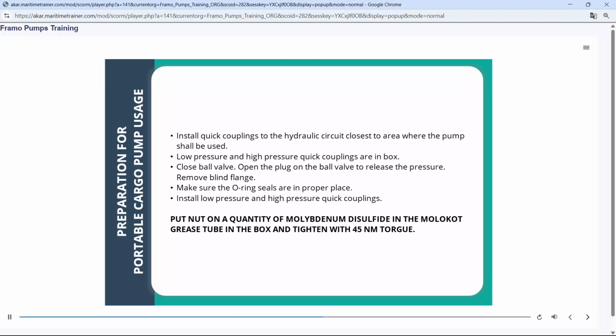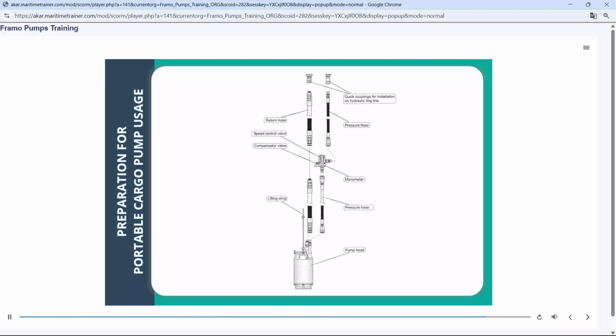Remove the blind flange. Make sure the O-ring seals are in proper place. Install low pressure and high pressure quick couplings. Put a quantity of molybdenum disulfide grease from the grease tube in the box on the nut and tighten with 45 Nm torque. You can examine the figure to understand well.